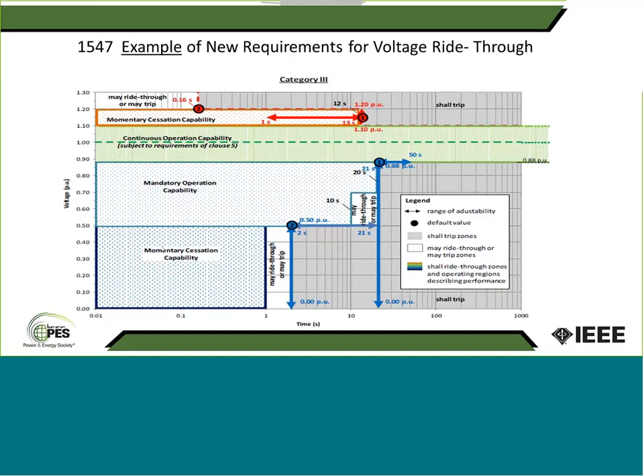So right now there's this 5 minutes reconnection time, and all that's going away with this concept of momentary cessation if there's no physical trip. So this is actually very important. The momentary cessation is something that we used in Massachusetts to resolve some of the distribution system protection issues, which I'm going to cover later on. So that's the reason that I put it in here, to make sure we're familiar with the concept. And then, the gray area is shall trip, which is self-explanatory, and I think that's it for this figure.